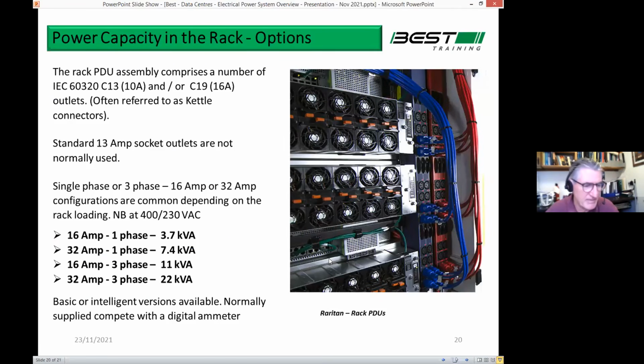And finally, into the back of the server, we're nearly here, so slightly over time. The power comes down from the bus bar and it feeds into these power strips. You can see them here. One is in blue again, and one is in red in the back of the server rack. They are just like the multi-block you have on your desk with a strip of sockets. It's an intelligent version of that. All the sockets are monitored, and the power can be measured through them.